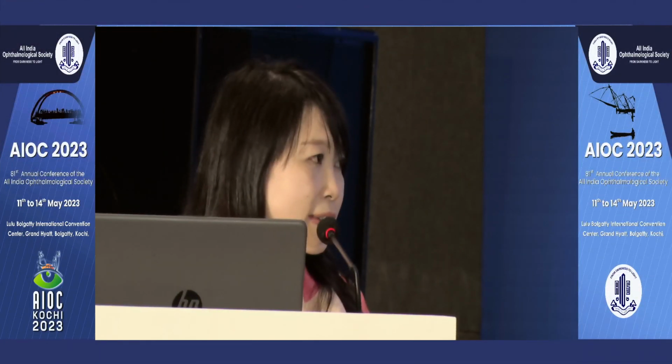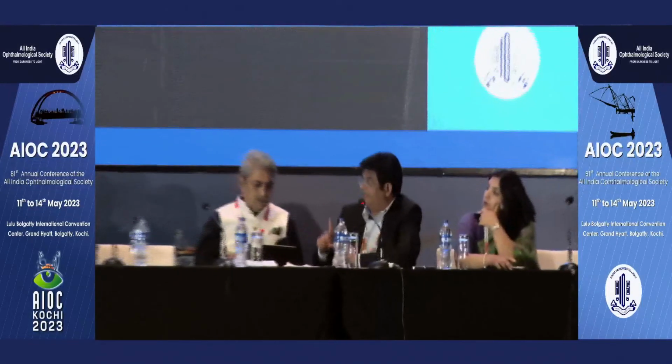In case there's a disagreement between Pentacam K1, K2 values and the Casia 2 K1, K2, which would you choose between the two? If there's a disagreement in the K1, K2 values and the axis, for example, you have a patient for toric IOL or something like that, which would you choose?